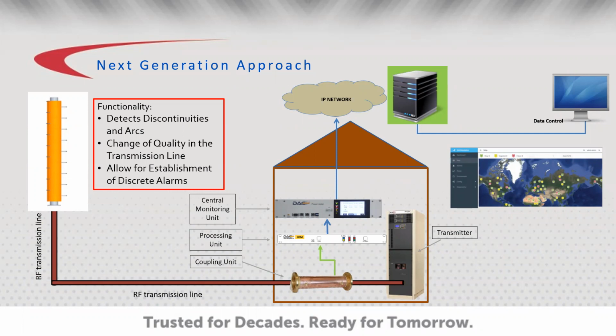The strategic placement of the coupling unit after the coax switch allows for the continuous monitoring of the system, whether or not it is in operation. So this will continue to monitor your transmission line, whether there's full power from the transmitter or no power at all. The results of this can be very telling, identifying temperature dependent mismatches by comparing measurements while the system is off and after while it's cooled down, or vice versa. Traditional TDR measurements cannot achieve this because the system will have already cooled down by the time the test setup is complete.